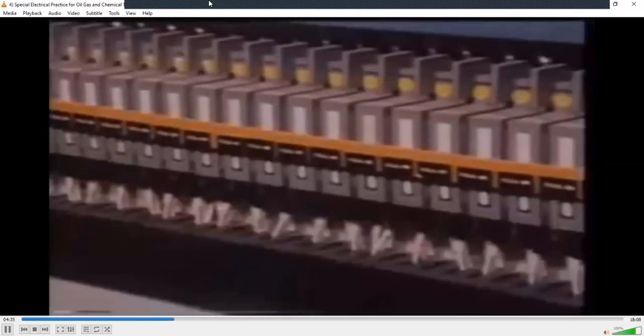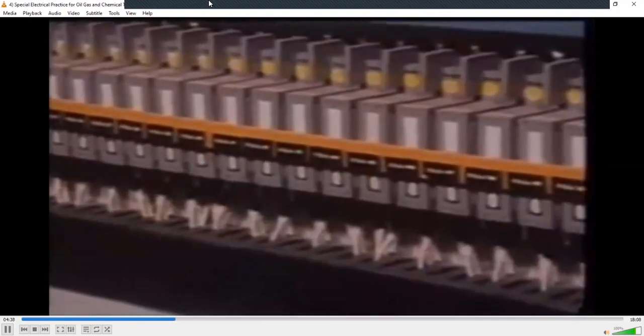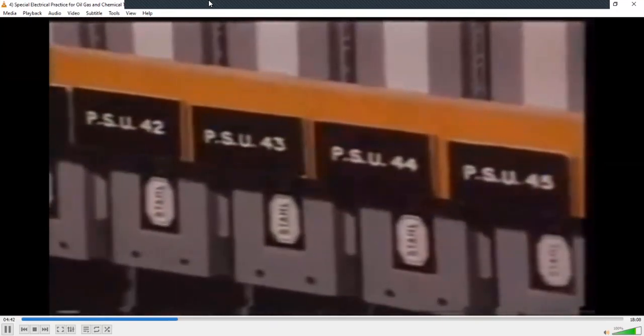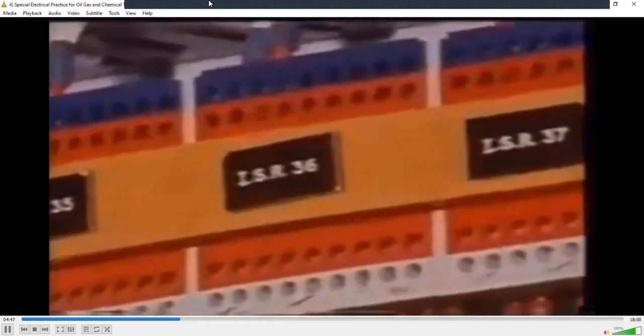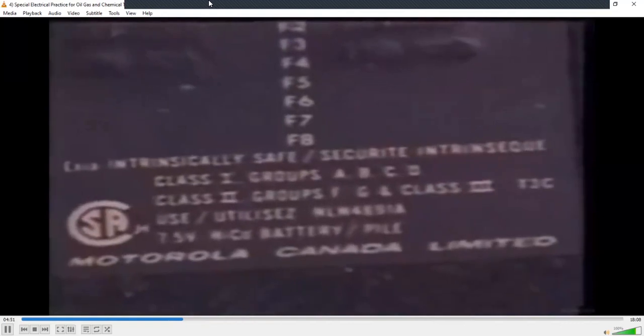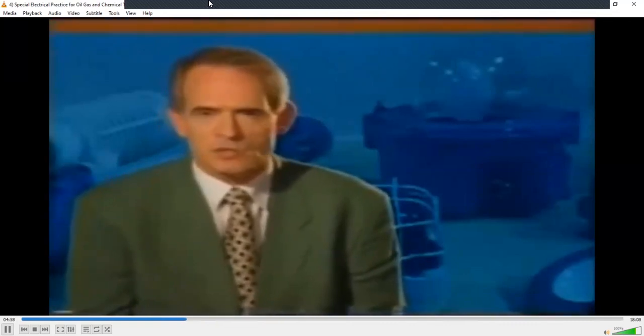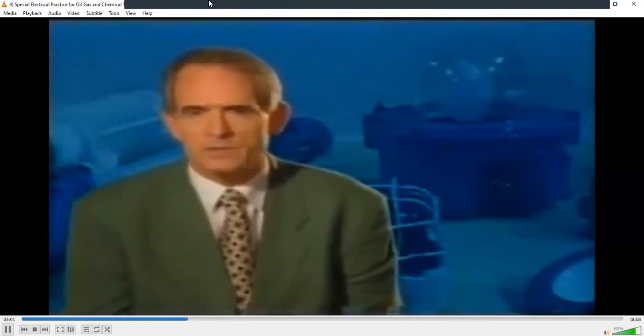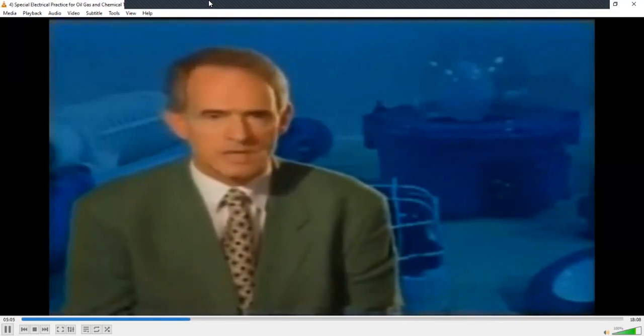They will have their own separate power supplies and a Zener protection barrier. The Zener barrier ensures that the maximum preset voltage in the circuitry cannot rise above the prescribed safety level, which ensures the certification of intrinsically safe, EXI. EXI, or intrinsically safe equipment and circuitry, has a protection technique which confines the energy within the system below a level which is capable of causing an explosion in a dangerous atmosphere.